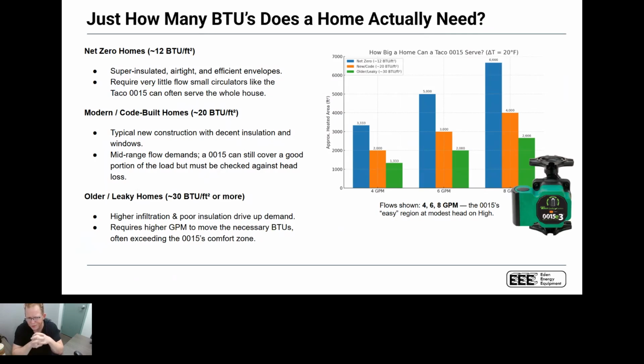If you look at houses that were built in the 80s, yeah, you might have 25 to 30 BTUs per square foot. But if you look at modern homes and how they're being built, especially as you get into near net zero, which is a very, very popular term with builders, the loads are getting smaller and smaller. Like 7 to 12 BTUs per square foot is not unheard of. So when we see a 5-ton heat pump, which is roughly 60,000 BTUs, we usually go, well, that's nowhere near big enough. I've always put in a 115,000 BTU IBC, Navien, whatever brand you put in.